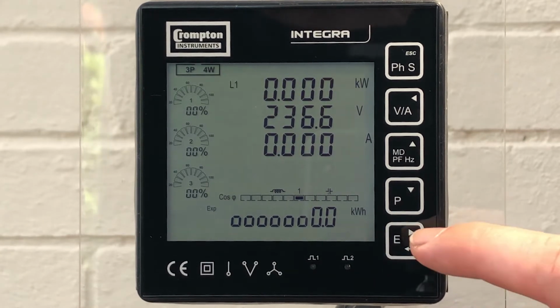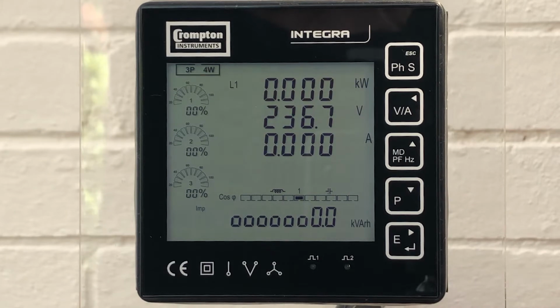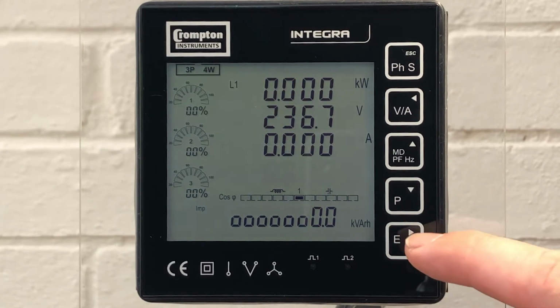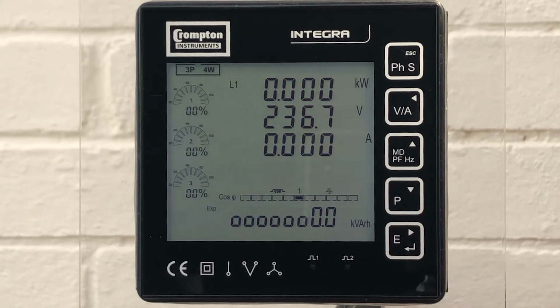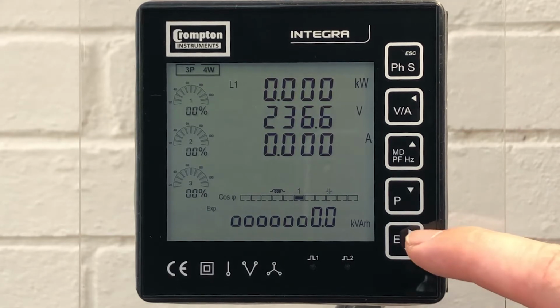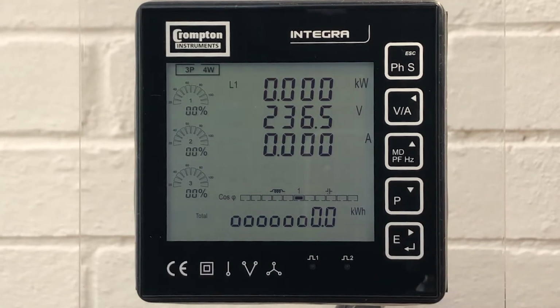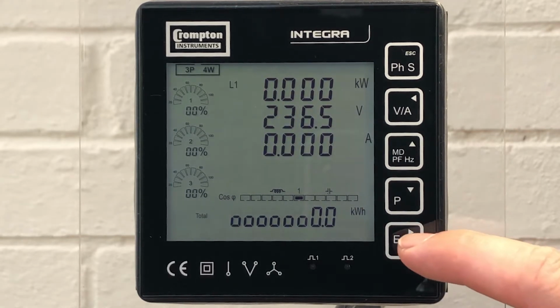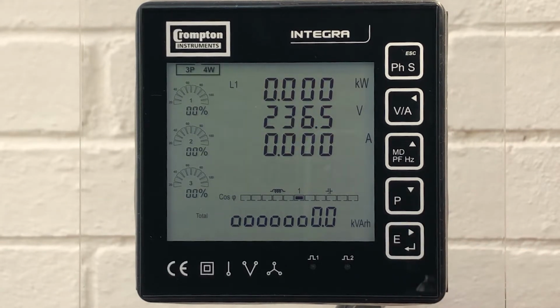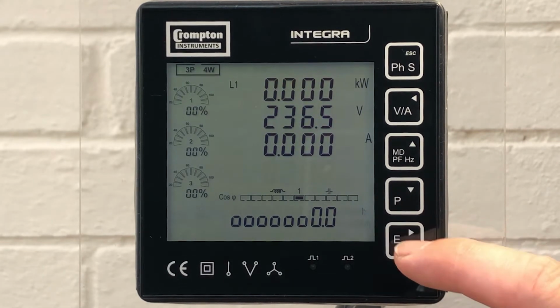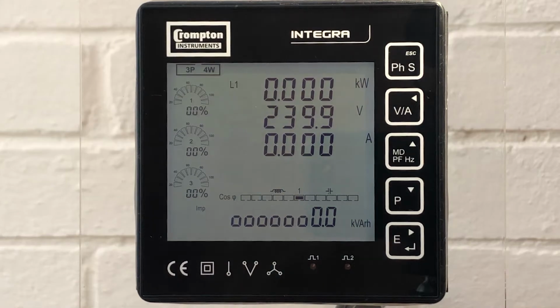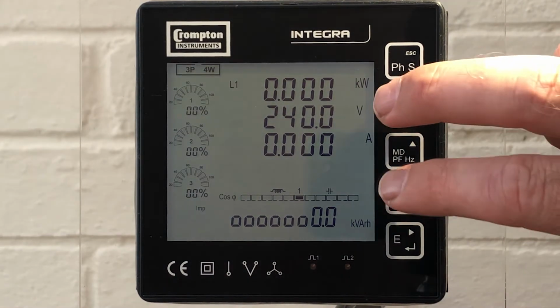A press of the E button shows us the imported kilowatt hours, kVAR hours, export kVAR hours, and the total kilowatt hours and the total kVAR hours. Whatever you leave this setting on is the setting that Integra will keep.